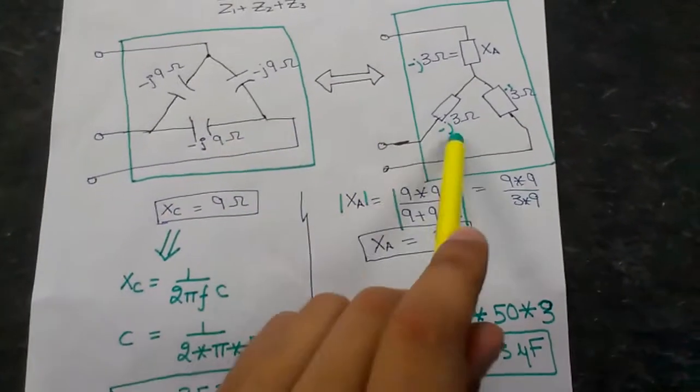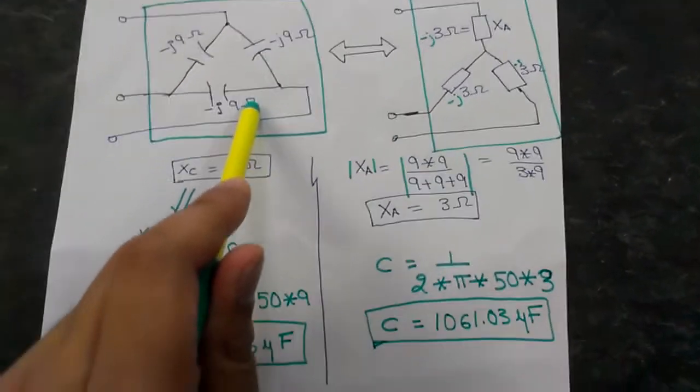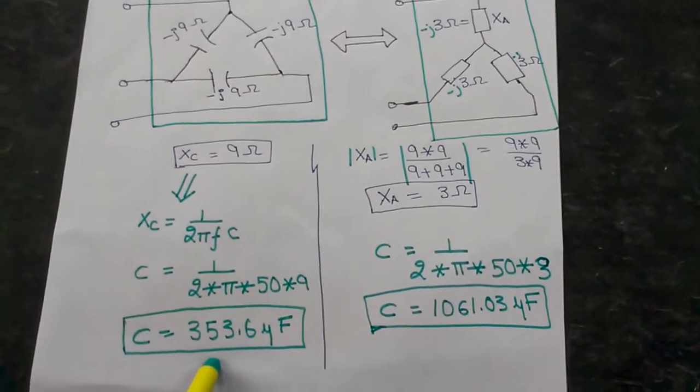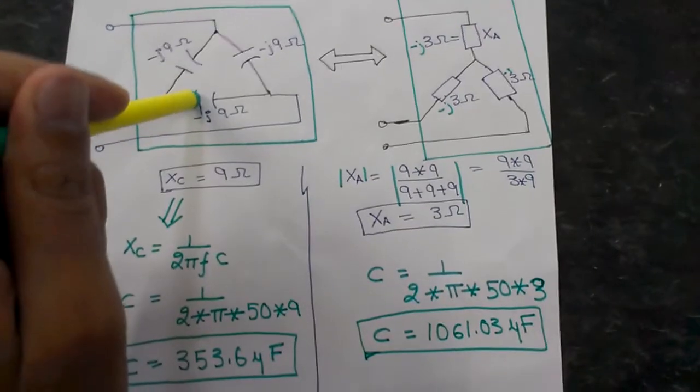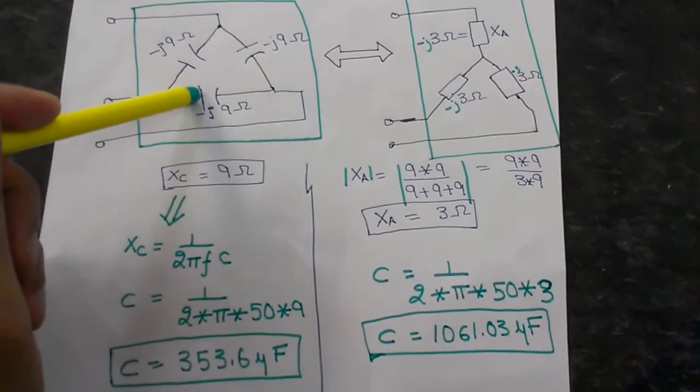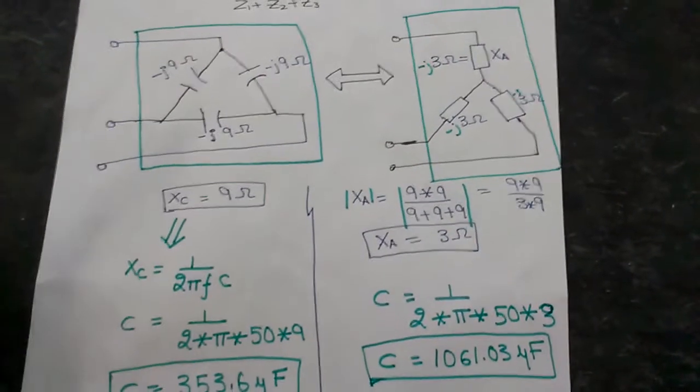So if the reactive power they are going to provide is equal, but here you see the capacitance value that you need is less for the Delta configuration, so that means this configuration will be cheaper as compared to this configuration, and that is the reason.